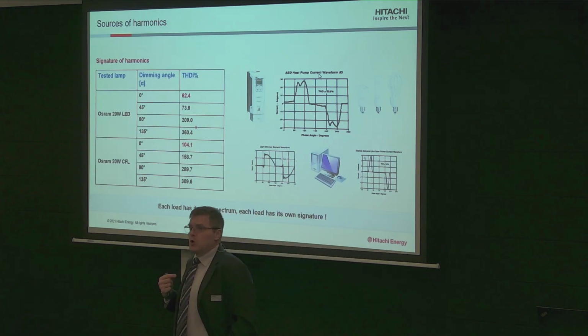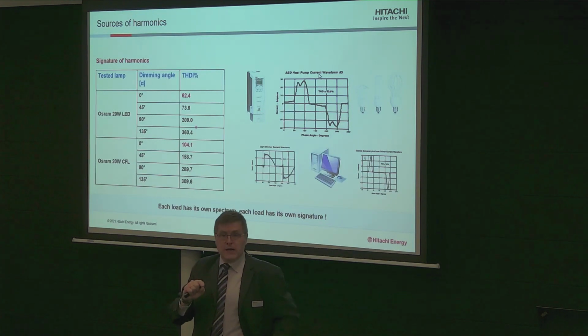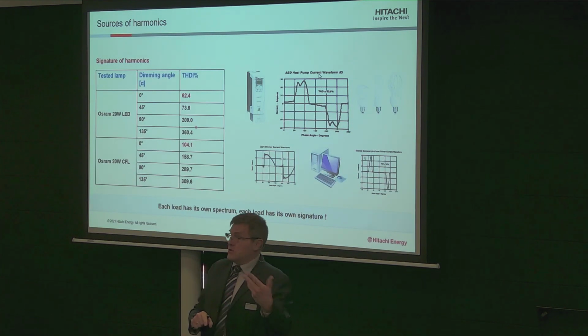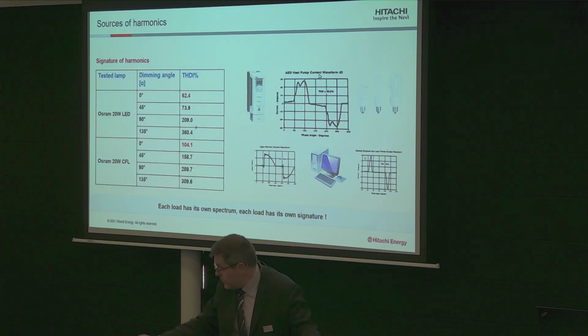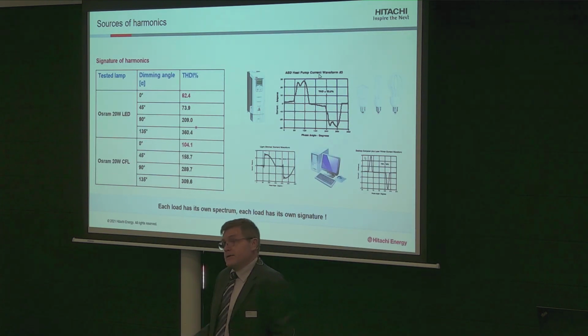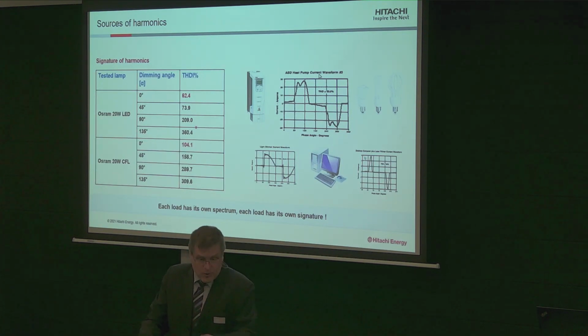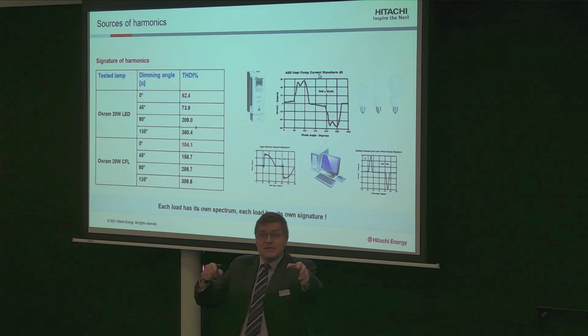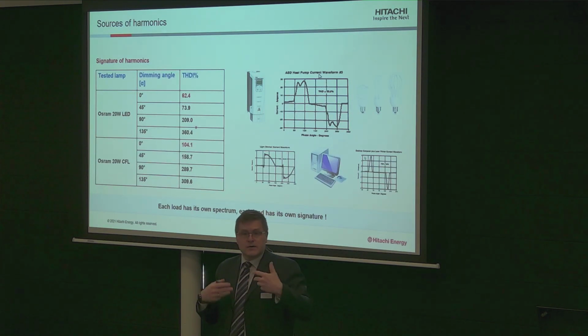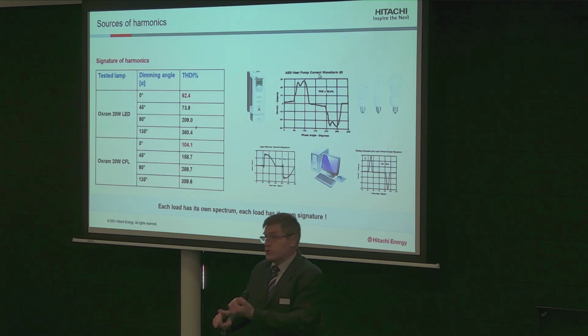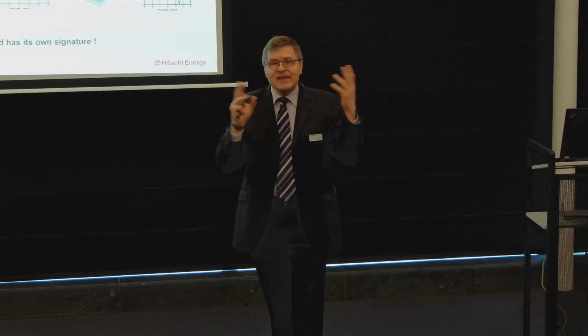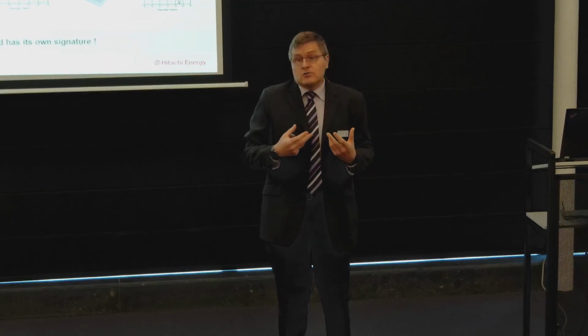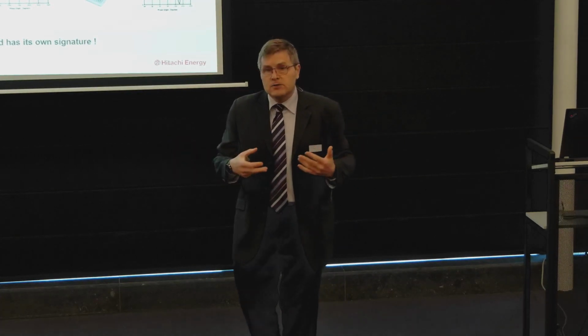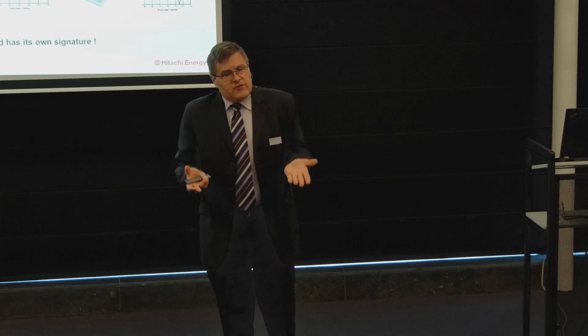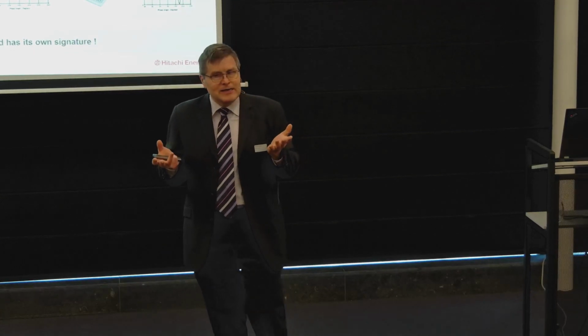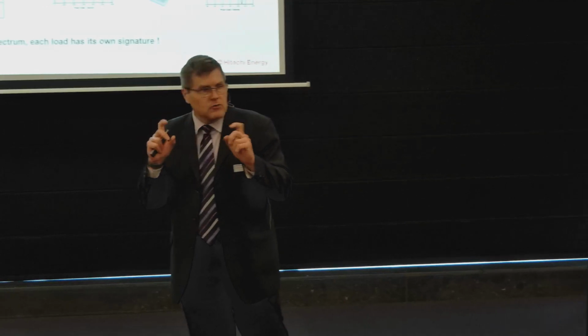But the problem is that with Ohm's law, if you have a current which is non-sinusoidal, it will generate a voltage which is non-sinusoidal. And if the voltage is distorted, all the other loads connected to the same grid will be disturbed. So the higher the current pollution, the higher the THDV, and the more pollution you have. That's the problem, because with immunity and emission, if the level of pollution is too high, then we start to have some problems. Today, the modern loads, motors, LEDs, computers, any load you can think of, use power supplies which are non-sinusoidal, and so the harmonic pollution is increasing on average. We need to look at that, because when the level of pollution reaches a certain level, this level is lower than the immunity level the equipment should have.